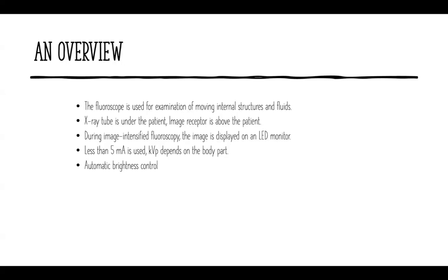During image intensified fluoroscopy, the image is displayed on the LED monitor. So instead of how we may take X-rays and they show up on the monitor, we have a special LED monitor that the digital images show up on. Usually with fluoro, we're using less than 5 mA, and the kVp depends on the body part.